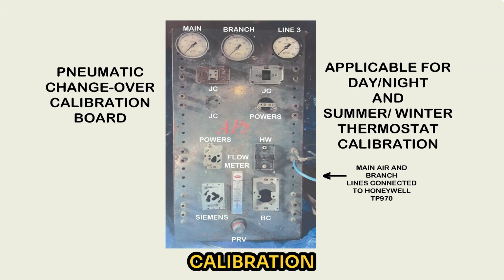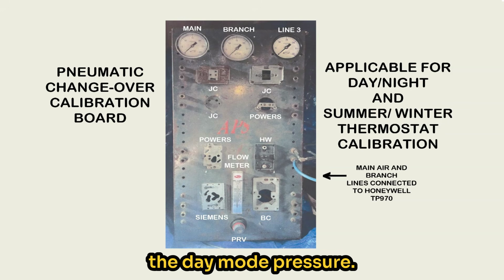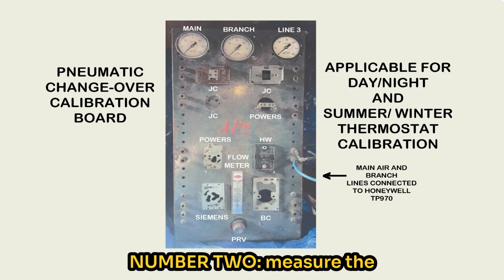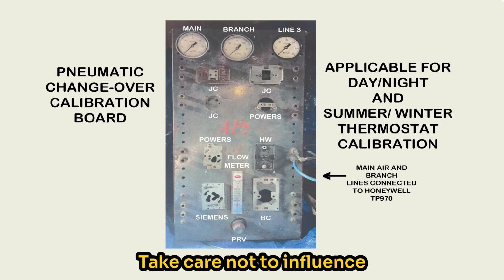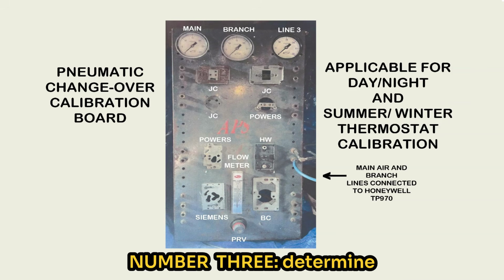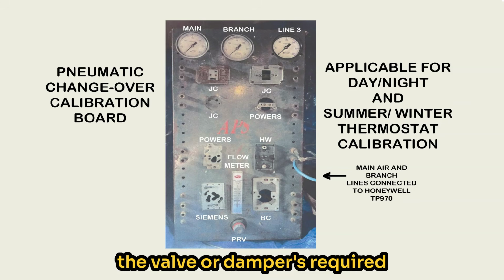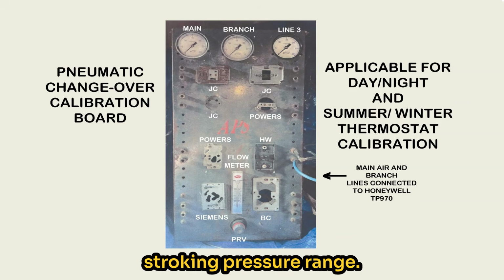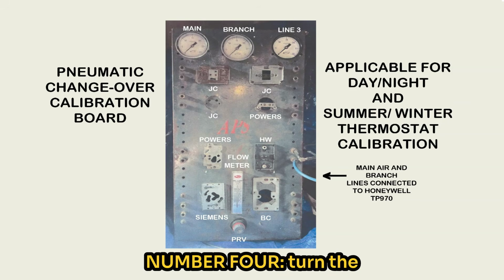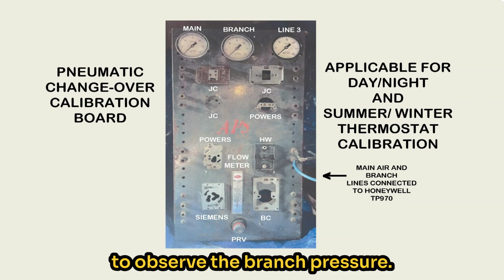Day-night temperature calibration, 1 dial to adjust. Calibrating day settings. Number 1. Set the main air pressure to the day mode pressure. Number 2. Measure the temperature at the thermostat. Take care not to influence the thermostat with your body heat or your breath. Number 3. Determine the valve or damper's required stroking pressure range. Number 4. Turn the thermostat setting up and down to observe the branch pressure.